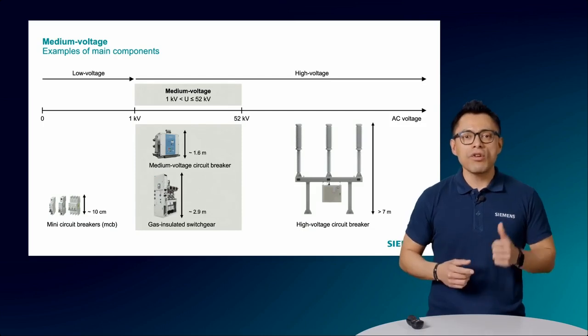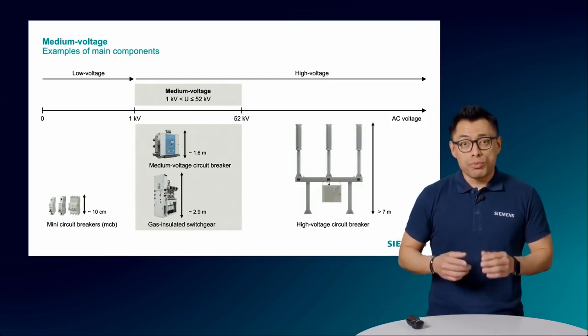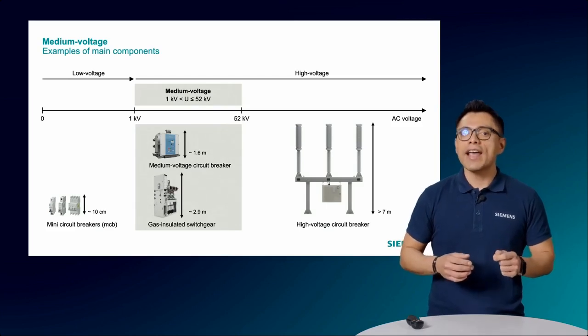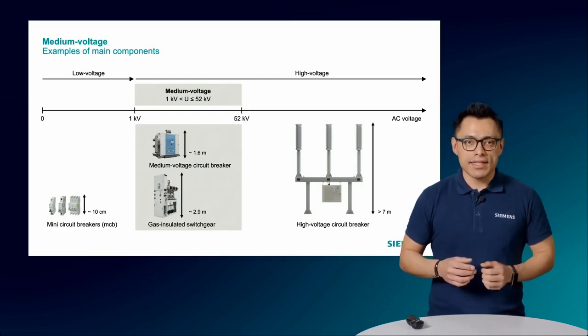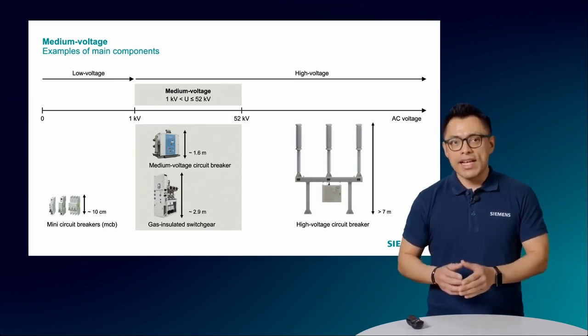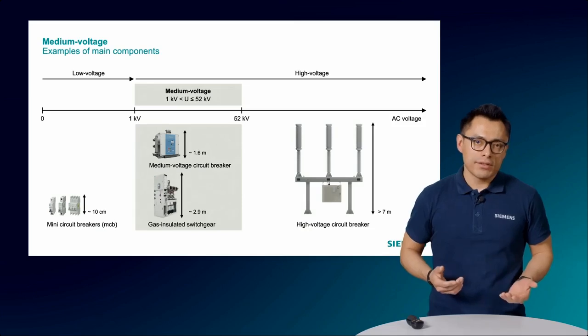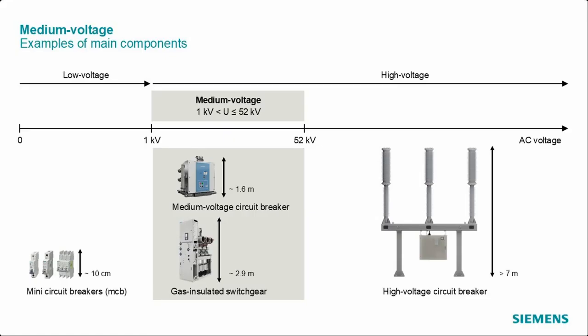A second factor is clearance and creepage distances. To prevent arcing and ensure safe operation, higher voltage equipment needs greater distances between conductive and grounded parts, leading to larger physical dimensions. A third factor is heat dissipation. Higher voltage equipment often generates more heat, which requires larger components and cooling mechanisms to dissipate this heat effectively. And the last factor is mechanical strength. Equipment operating at higher voltages needs to withstand higher mechanical stress, which can result in larger and more robust designs.